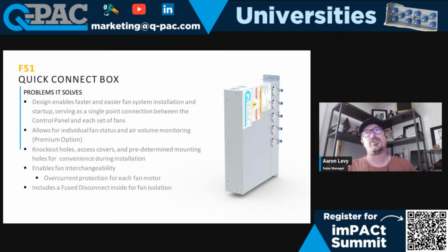So sometimes you'll see fan alarms come in on your controller. Sometimes it's just a fuse that's popped inside this box because it was trying to save something from getting to the fan. So it's always probably the first point I would look at if you see a fan alarm and you're checking power: make sure you have all 3 legs. And if you don't, go back to this point and start troubleshooting from there.